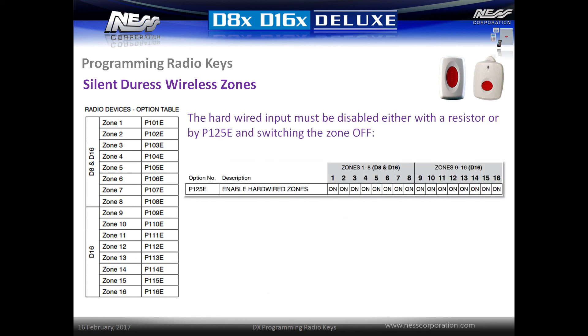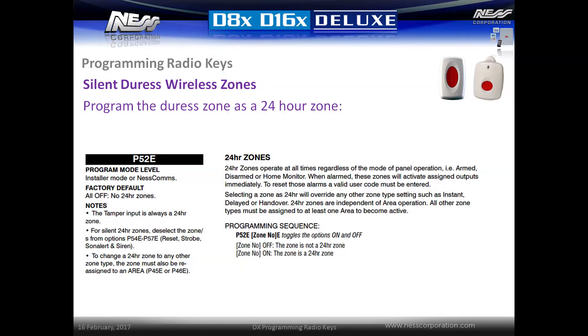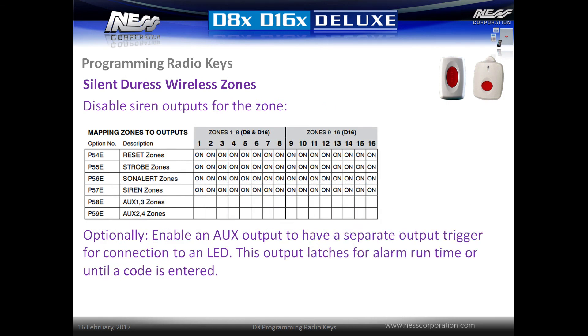Next, disable the zone's hardwired input by placing a resistor into the zone or deprogramming it via option p125e, then deselect the zone followed by E. Program the zone as a 24-hour zone by entering location p52e and activating the zone followed by E. Disable the siren outputs for the zone in locations p54e through to p57e — you can selectively choose which siren outputs to enable or disable for the radio zone. Optionally, an auxiliary output could be enabled for the zone and connected to an LED indicator, which will latch for the siren runtime or until reset by a code, serving as a visual indicator that a duress has been triggered.